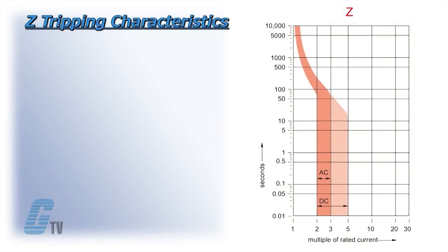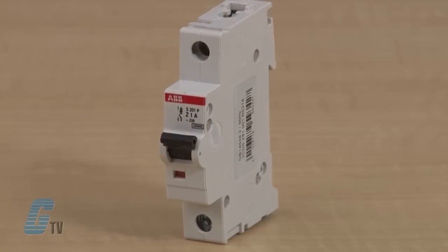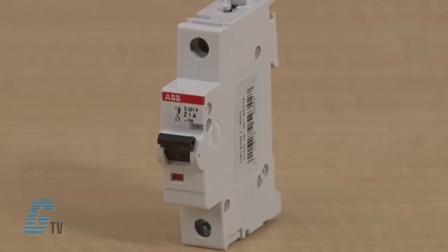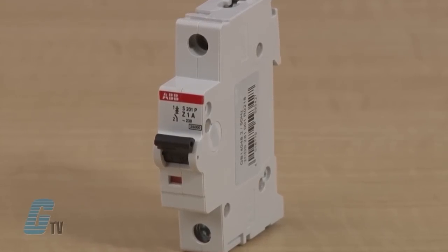Breakers with the Z tripping characteristic are available up through 63 amps. The Z characteristic offers instantaneous tripping between 2 and 3 times rated current in 50 or 60 Hz systems. Many applications require very low short circuit trip settings in order to protect semiconductors or other sensitive devices and the Z trip characteristic may provide maximum protection and service for these applications.